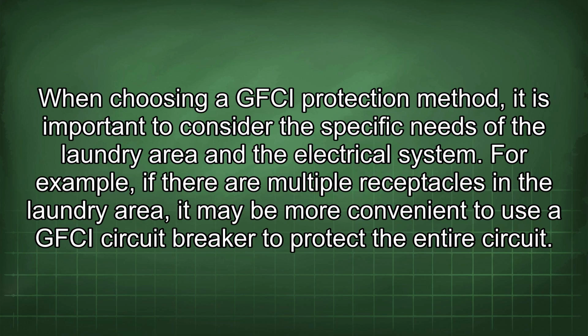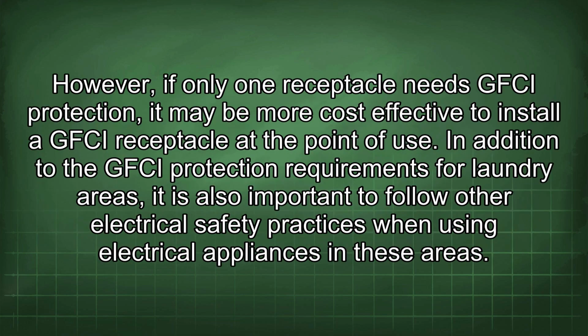For example, if there are multiple receptacles in the laundry area, it may be more convenient to use a GFCI circuit breaker to protect the entire circuit. However, if only one receptacle needs GFCI protection, it may be more cost-effective to install a GFCI receptacle at the point of use. In addition to the GFCI protection requirements for laundry areas, it is also important to follow other electrical safety practices when using electrical appliances in these areas.